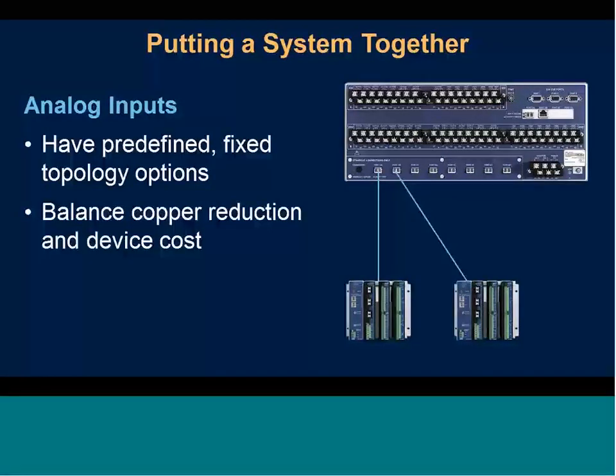The trade-off is these are predefined topologies, so you have to connect them a certain way, and they're fixed. We generally look at two aspects when defining these topologies: copper reduction and device cost. Copper reduction means I can reduce the amount of copper I have to run around my substation by putting the device close to where it needs to be. But the flip side is I'd have to buy more devices, so there are also topologies we created to address that, where we have fewer devices with the trade-off of running more connections to those devices. In a couple slides, we have some example topologies to show what we mean by this.